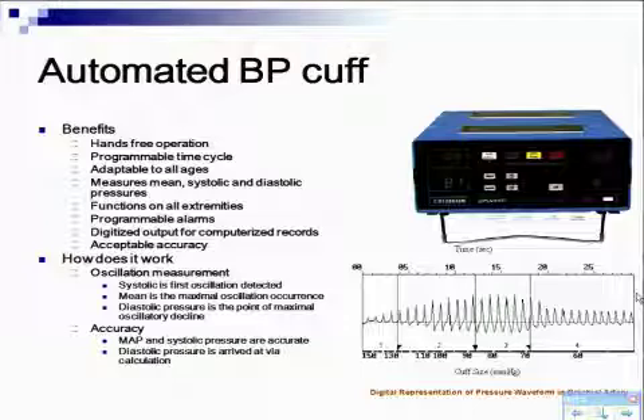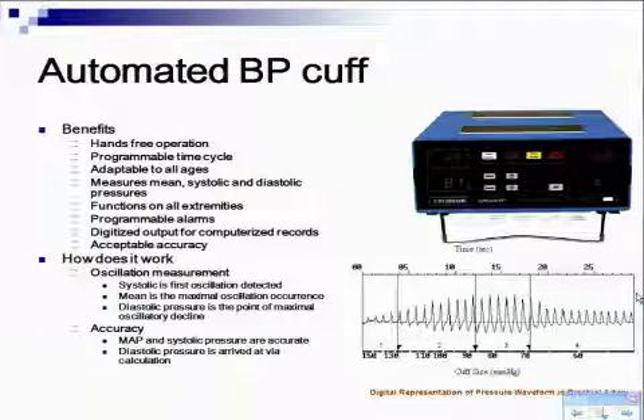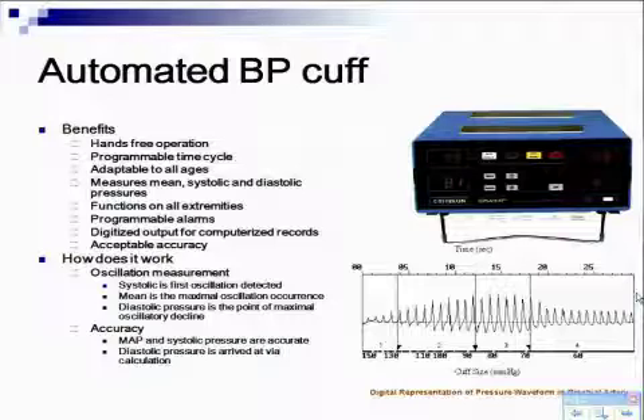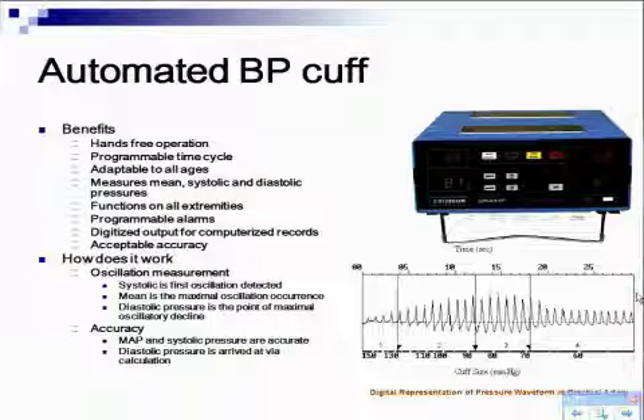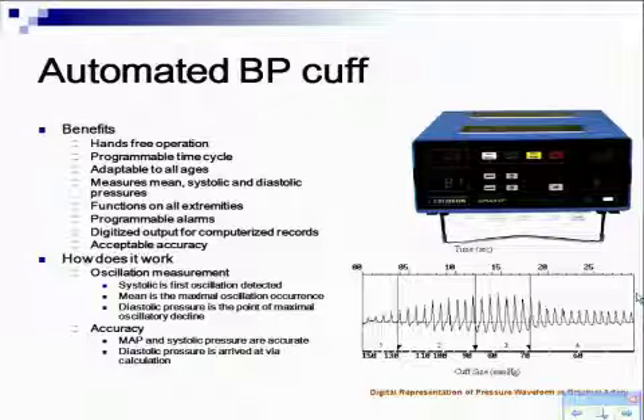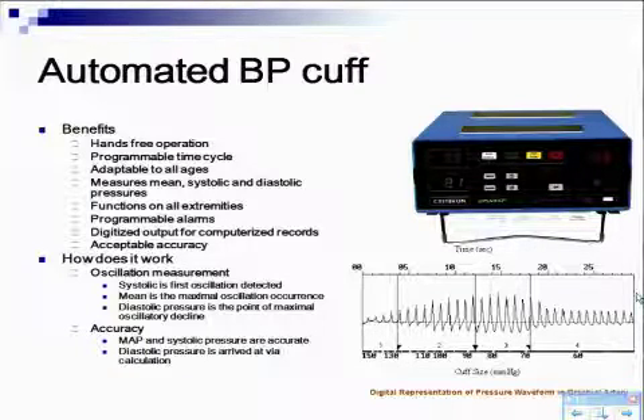And what the machine does is it mathematically figures out diastolic pressure. So diastolic pressure is completely a figment of our imagination. It has never been mathematically proven to be correct. No study's ever been done on it, and nobody gives out their data as to how they measure it. In other words, they don't give you the mathematical formula. It's considered a patent, so you're not able to even look at it scientifically. But we do know it correlates fairly well. When we do A-lines, it correlates pretty well. The good thing about automated blood pressure cuffs is it's hands-free operation, programmable, adaptable to all ages. It measures mean, systolic, and diastolic pressure, but really measures only 2 of them, mean and systolic. It functions in all extremities and has programmable alarms.